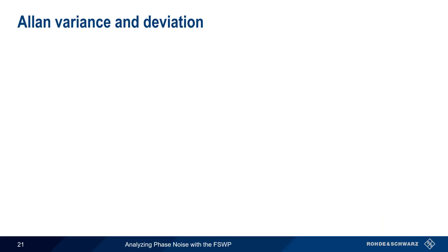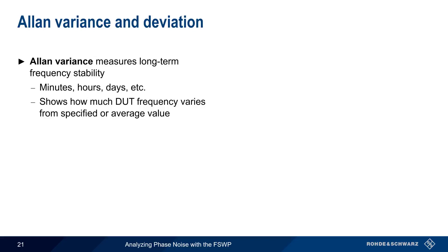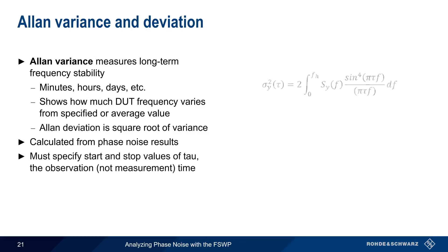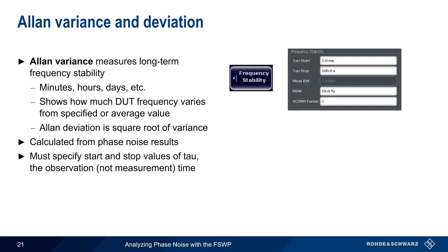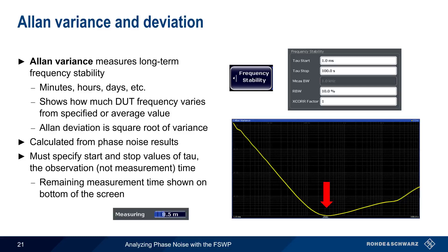The final measurement we'll look at is Allan Variance or Allan Deviation. Unlike phase noise, which is a measure of short-term frequency stability, Allan Variance measures long-term frequency stability — with long-term being on the order of minutes, hours, days, etc. Allan Variance shows how much the DUT frequency varies from the specified or average value. Note that Allan Deviation is simply the square root of Allan Variance. The FSWP calculates it directly from the phase noise results. The only thing you need to specify are the start and stop values of tau, the observation time. Allan Variance measurements can take a long time to run, so the remaining time indicator at the bottom of the screen may be helpful.